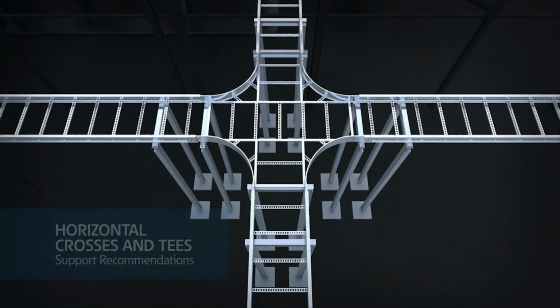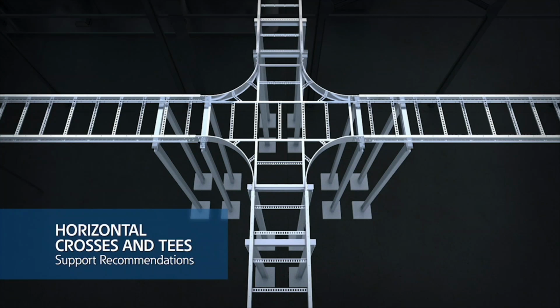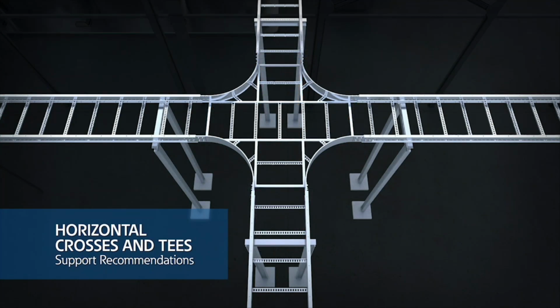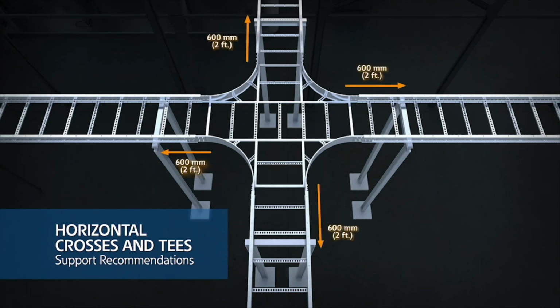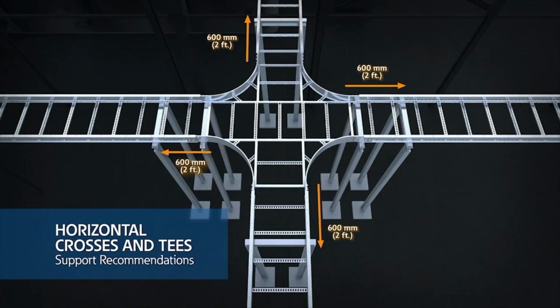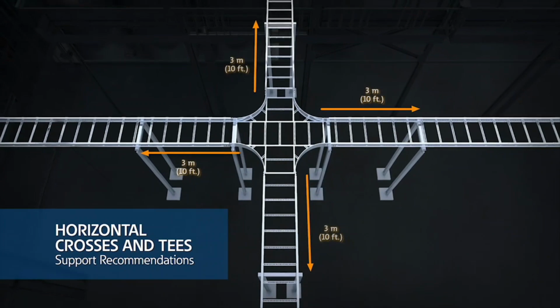For horizontal crosses and horizontal tees, supports for the fittings, normally 3 to 4, are not required if a support is placed within 600 millimeters of each splice point. Also, if supports are dedicated to the fitting, the B-Line series cable ladder system only requires 2 supports for the fitting, and the allowable range for ladder supports near the splices increases from 600 millimeters to 3 meters.